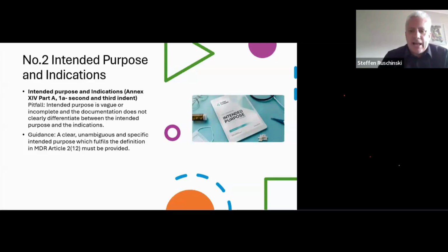So our clinical evaluation plan should clearly differentiate between the indications and the intended purpose. But in the absence of an MDR definition, manufacturers are directed to the MDCG 2020-6, where the indications are defined as the clinical condition that is to be diagnosed, prevented, monitored, treated, alleviated, compensated for, replaced, modified, or controlled by the medical device. And this should be distinguished from the intended purpose or intended use, which should describe the effect of the device.